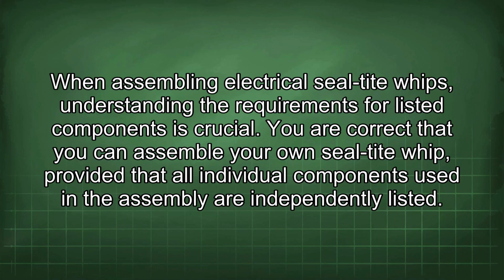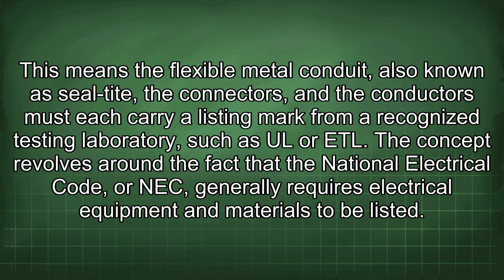When assembling electrical Seal-Tite whips, understanding the requirements for listed components is crucial. You are correct that you can assemble your own Seal-Tite whip, provided that all individual components used in the assembly are independently listed. This means the flexible metal conduit, also known as Seal-Tite, the connectors, and the conductors must each carry a listing mark from a recognized testing laboratory such as UL or ETL.